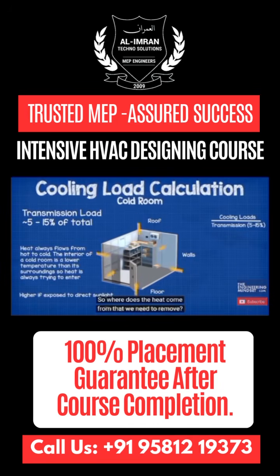So where does the heat come from that we need to remove? Well, typically 5 to 15% is through transmission loads. This is the thermal energy transferred through the roof, the walls and the floor into the cold room. Now, heat always flows from hot to cold, and the interior of the cold room is obviously a lot colder than its surroundings. So heat is always trying to enter the space because of that temperature difference.